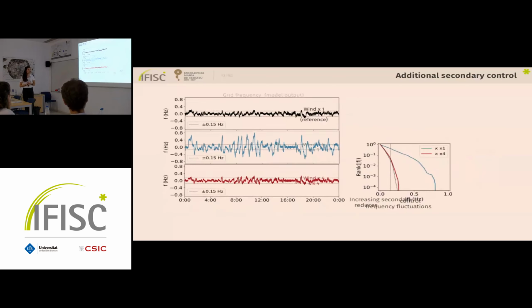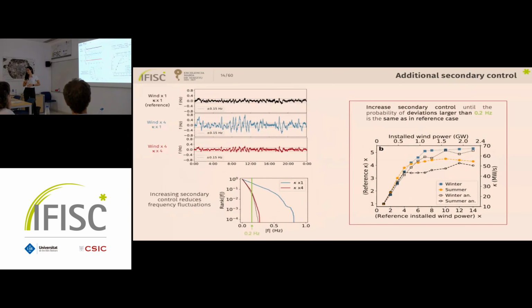So we were interested in estimating these additional control needs, and we did that both numerically and analytically, but I will not go into the details of the analytical estimation here, both for winter and summer. And as you can see here, numerically, we increased secondary control until the probability of frequency fluctuations larger than 0.2 is exactly the same as in the reference case. So basically, this vertical line marks that 0.2. And so we increase secondary control until the red distribution, which is the one with more control, crosses this vertical line as well as the reference distribution here.